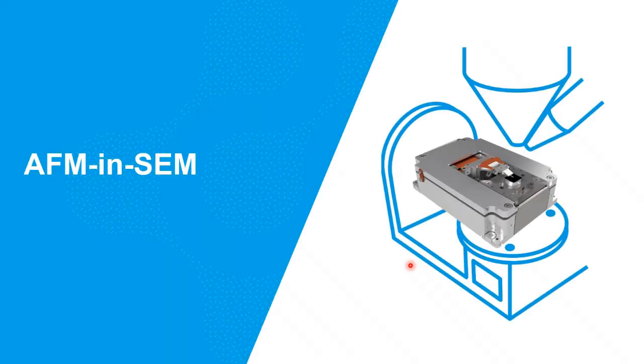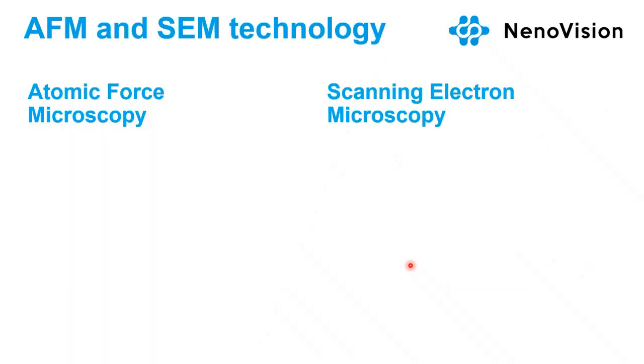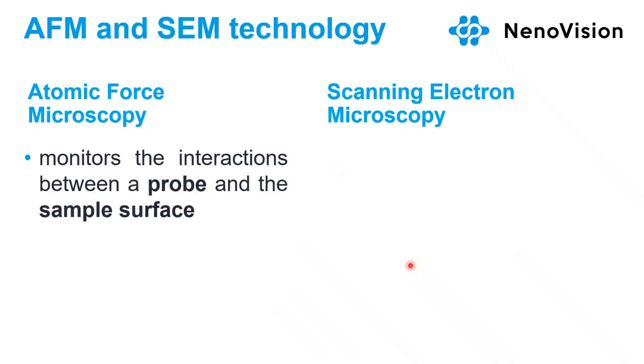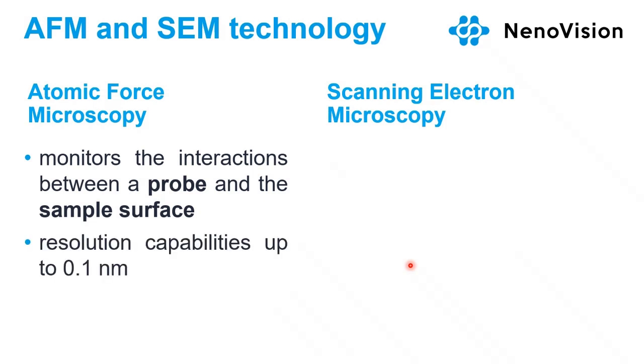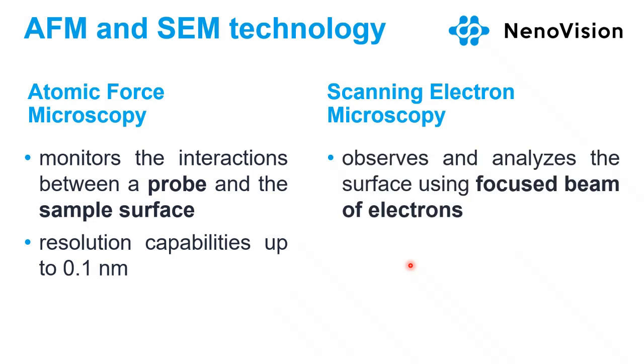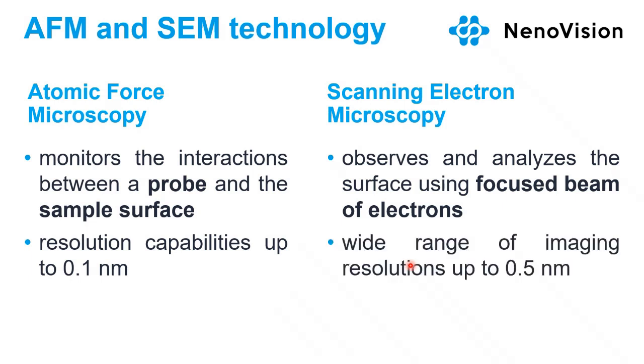So let's start with motivation, why we want to combine AFM and SEM technology. Atomic force microscopes and scanning electron microscopes are two of the most used and, in fact, complementary techniques for sample analysis in the nanoscale. Nevertheless, since the principles of how they observe and interact with the sample surface are completely different, they provide a very different set of information. AFM monitors interaction between a physical probe and the sample surface. It has very high resolution, up to 0.1 nanometers. Scanning electron microscope observes and analyzes the surface using a focused beam of electrons. So it has very good resolution in lateral dimensions, up to 0.5 nanometers.